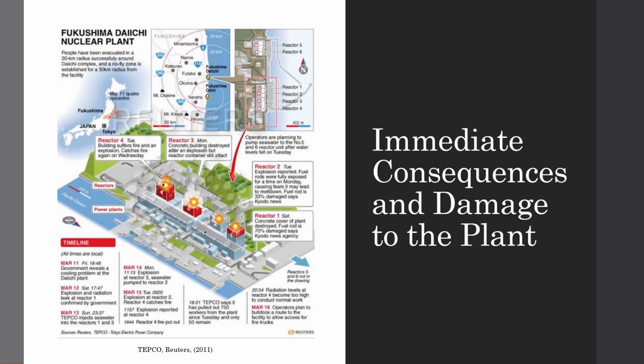Due to the blackout, operators were no longer able to monitor some of the essential plant parameters like reactor pressure and reactor water level. Unfortunately, there were no procedures addressing the loss of all AC and DC power to direct the operators on immediate actions. Now in a blackout, pumps had failed, control valves were left inoperable, and operators had become blind with the failure of instrumentation.